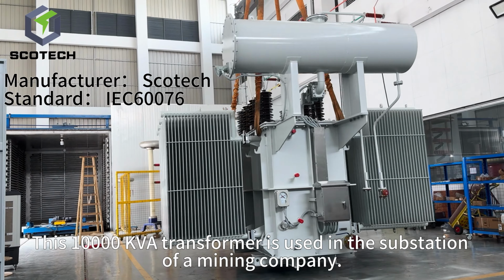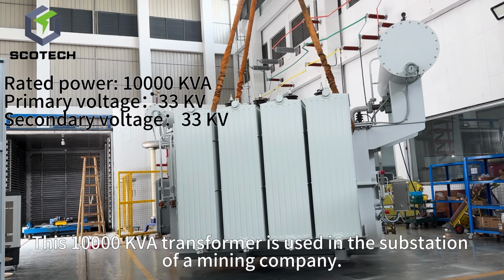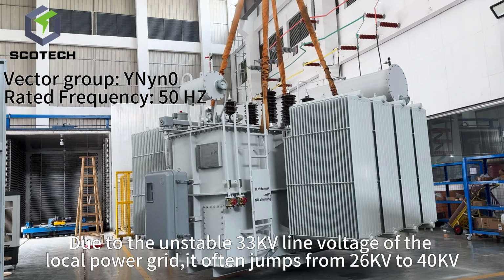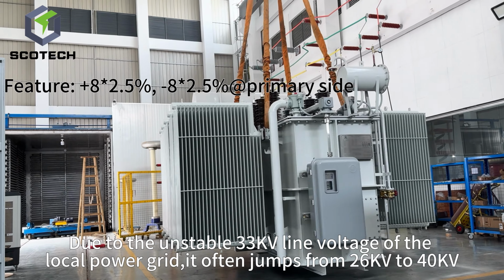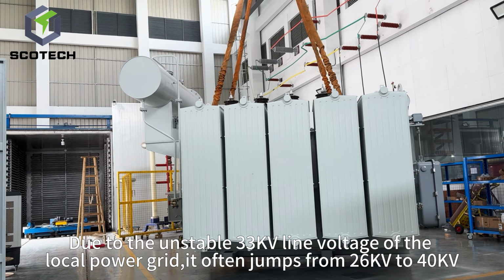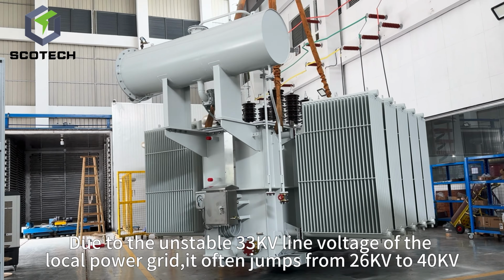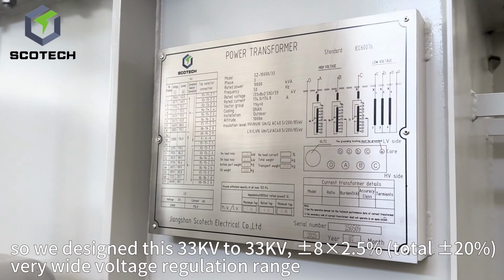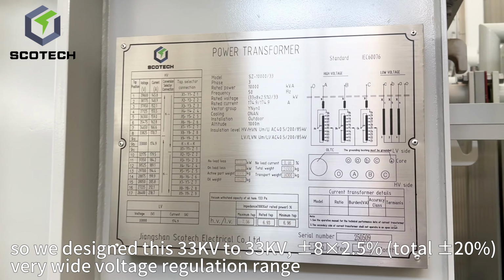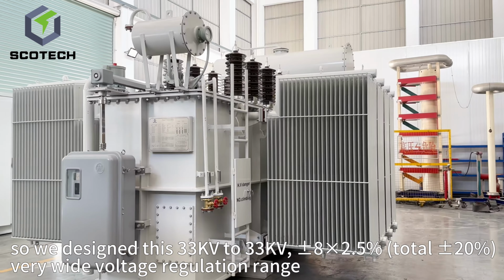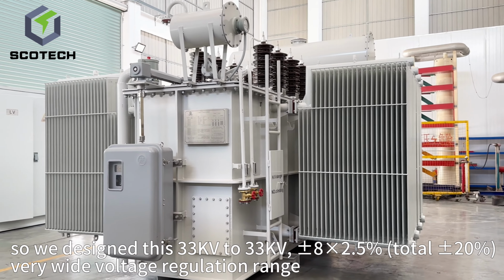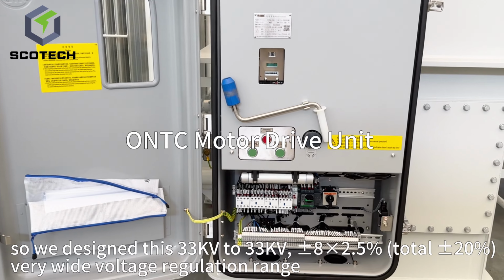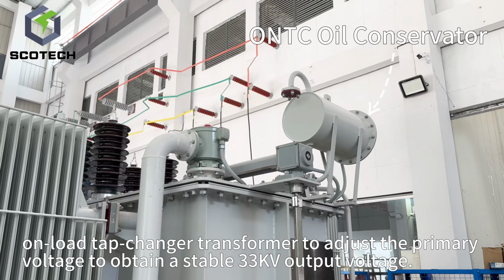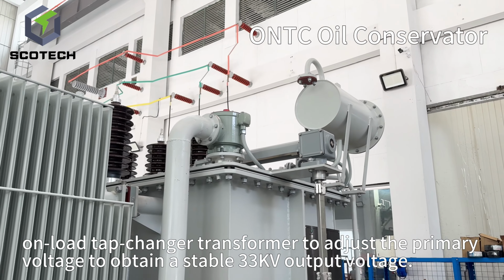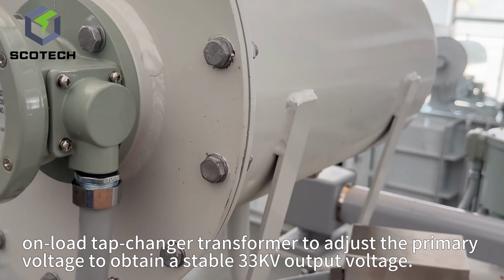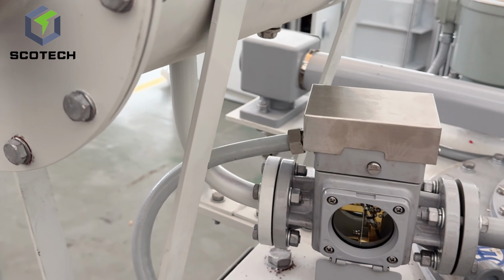This 10,000 kVA transformer is used in the substation of a mining company. Due to the unstable 33 kV line voltage of the local power grid, which often fluctuates from 26 kV to 40 kV, we designed this 33 kV to 33 kV plus or minus 8 times 2.5%, total plus or minus 20% very wide voltage regulation range on-load tap changer transformer to adjust the primary voltage and obtain a stable 33 kV output voltage.